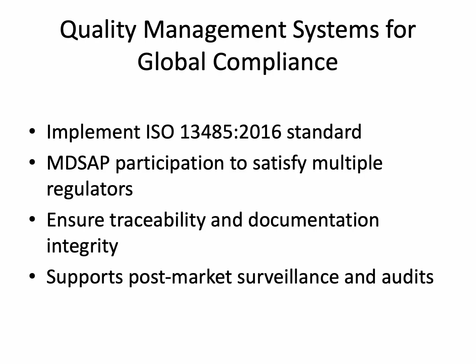Participation in MDSAP audits allows a single assessment to satisfy regulatory requirements in multiple jurisdictions, streamlining compliance and reducing duplicative effort. The QMS ensures traceability of design inputs, outputs, verification and validation, risk management, and post-market surveillance. Document integrity and controlled change management are critical to demonstrate compliance to auditors and regulators. Implementing a global QMS supports efficient regulatory submissions, continuous improvement, and timely response to post-market issues, ensuring ongoing device safety and efficacy.